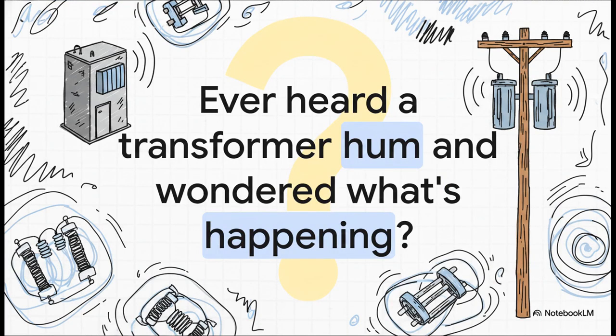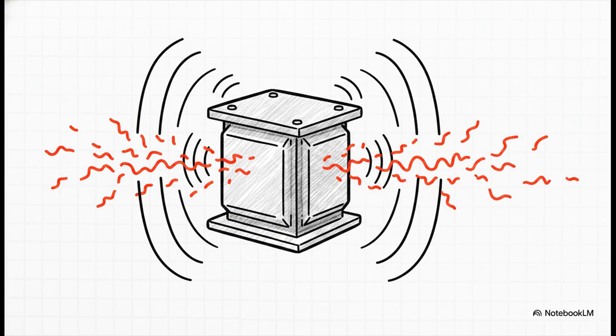Okay, let's start with something you've probably experienced. If you've ever walked past a big electrical substation, or even just a utility pole, you've heard it, right? That constant low-frequency hum? It's such a common sound that most of us just tune it out. But what if I told you that sound isn't just random noise? That's right. That hum is actually caused by something called magnetostriction. It means the transformer's metal core is physically vibrating, literally expanding and contracting with every single cycle of the alternating current. And that sound you hear, well, that's the audible proof of energy just leaking away into the air.